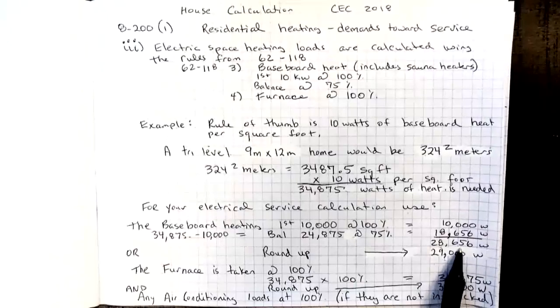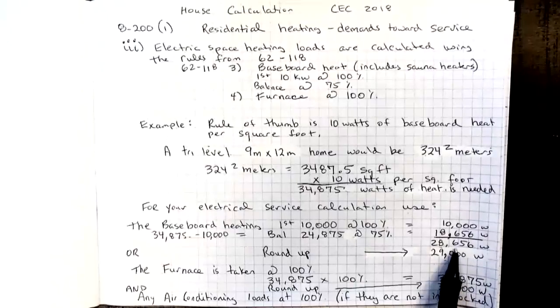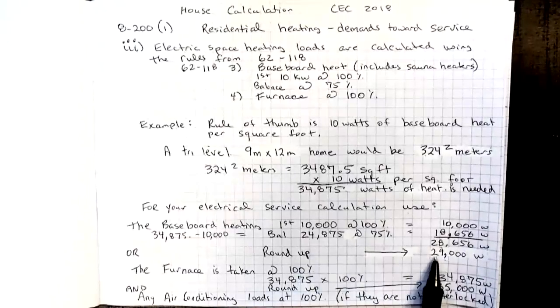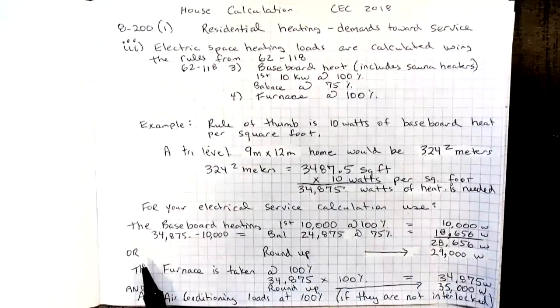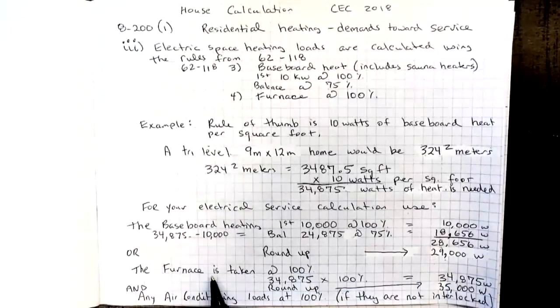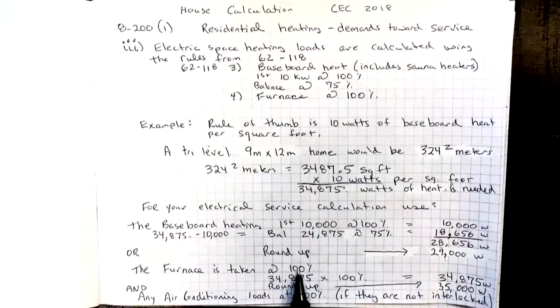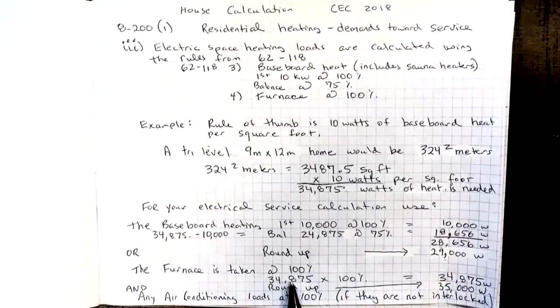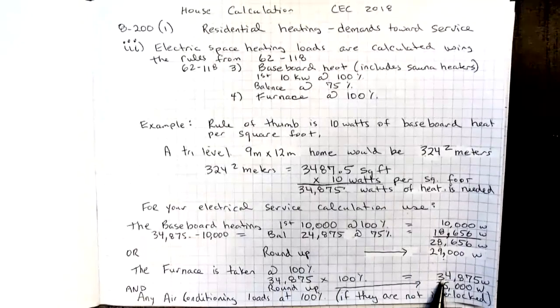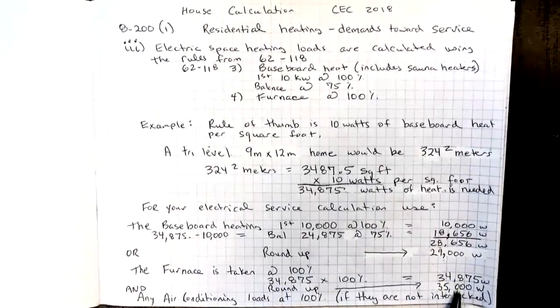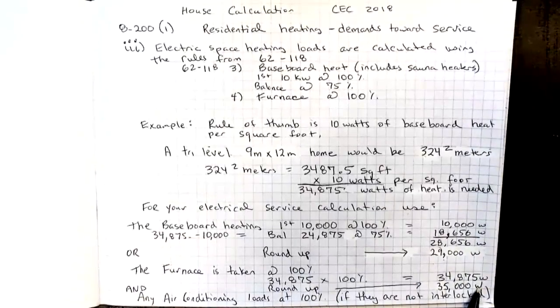That's an awkward number because baseboard heat doesn't really work out to odd numbers. So I would round up this number to 29,000 watts of heat. If I had a furnace in the home, the furnace is taken at 100%, I need 34,875 watts of heat times 100%, rounded up would be 35,000 watts of heat.